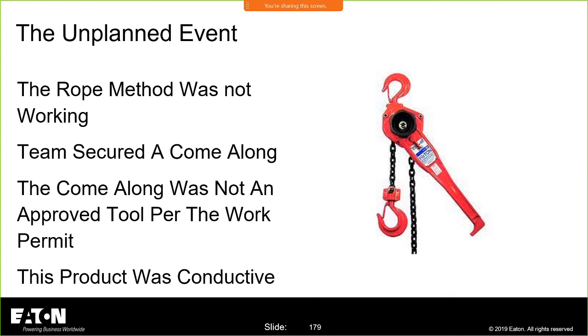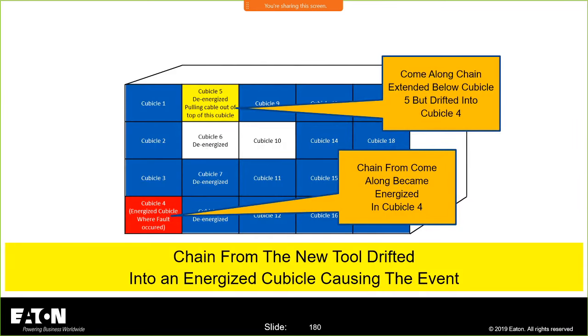They may have finished that job with that come along, but somebody probably would have been in charge of the end of that chain because nobody was. And what happened was the chain dropped down, it went over and into an energized portion of the assembly. Now, that would have been a very large explosion. That's a very high incident energy calculation, and there were intentional delays upstream.